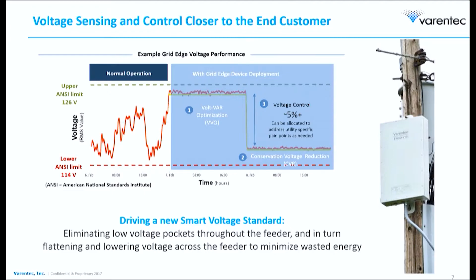This is just to give you a flavor of what the system does. I'm not going to go too much into the details, but if you look at the first section, the voltage throughout the day, how it fluctuates, it goes from maybe 125 to very close to 130, or 115 volts. Now, when we activate the system, the second part, you can see how closely the voltage is kept to its set point, the yellow line just below these points, and this is real-time data. The whole concept is once you get that, you get to the third section where you get the room to drop the whole voltage and really capture all these benefits. This is what we try to claim as the new smart voltage standard. You flatten the voltage throughout the feeder, and in a way you maximize your energy efficiency and minimize your wasted energy or losses in the distribution grid.